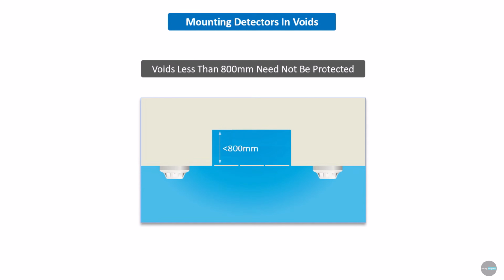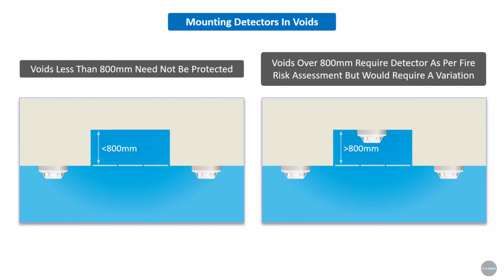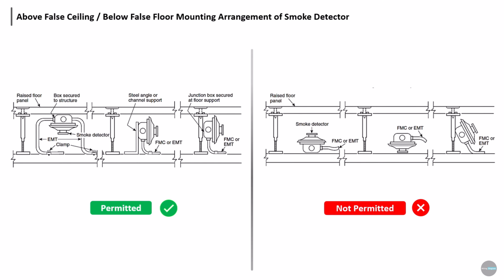Mounting detectors in voids. First, if the void depth is less than 800 millimeters, detector installation is not required. Second, if the void depth is more than 800 millimeters, provide detector coverage according to fire risk. If a detector is installed above a false ceiling or below a false floor, then the detector must be mounted in that same arrangement. Installing the detector in any other position is not permitted.